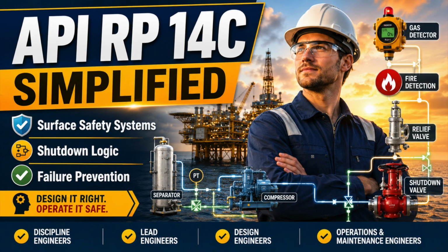Design the process to be inherently safer before adding instrumentation. Identify the failure before selecting the device. Use independent protection where failure consequences are serious. Stop hazardous energy at its source. Do not create new hazards through shutdown action. Treat piping, backflow, and trapped inventory as part of the protected system. Design ventilation, detection, containment, isolation, and relief as one integrated architecture. Make every safeguard testable. Document why every device exists and why every expected device has been removed. Revalidate the safety logic whenever the process changes.